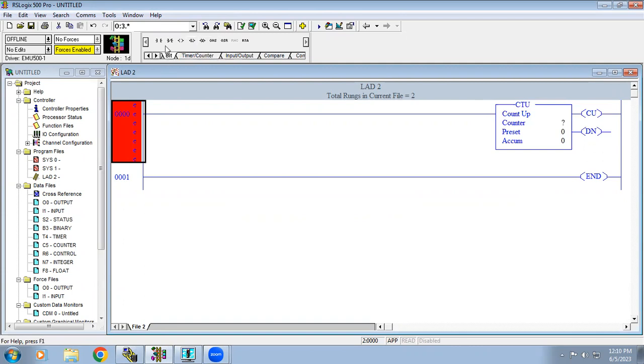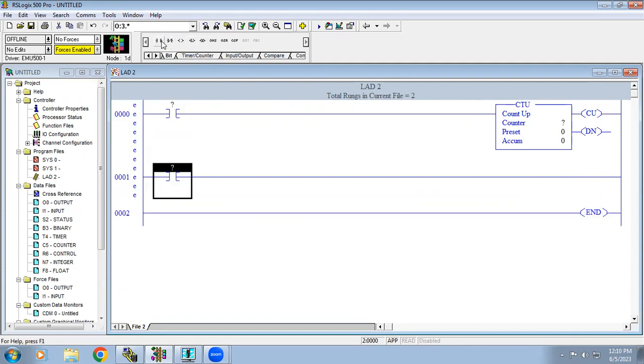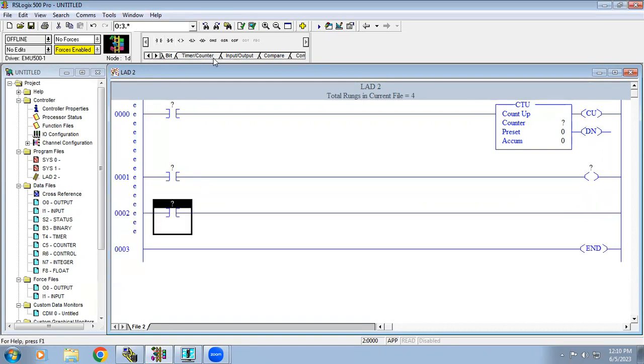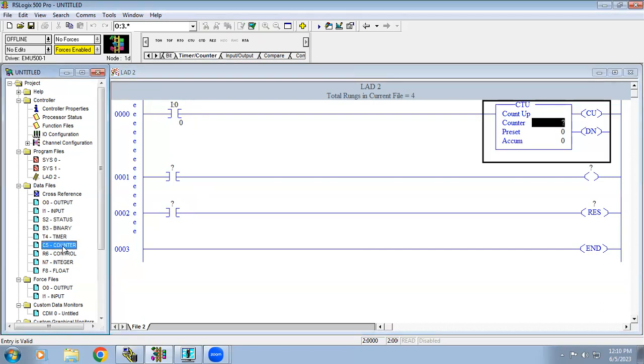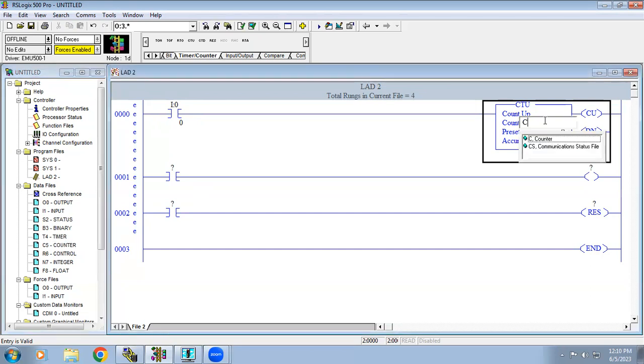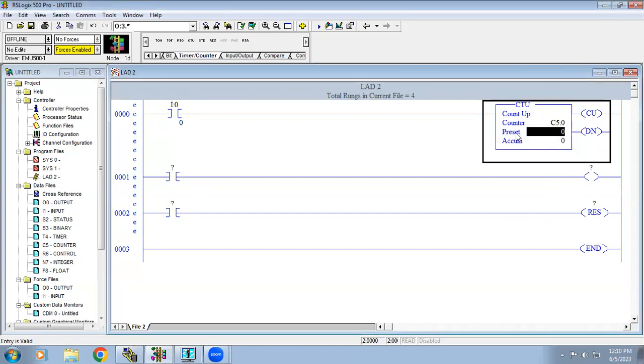I will place the input. When using the counter, we definitely need a reset function to reset the counter, so a separate rung has been added. For the counter input, the address has been given as C5 colon 0. When you type C, it will automatically show the counter and the address C5 colon 0. Then we set the reset and the preset count — I am setting 5 counts.